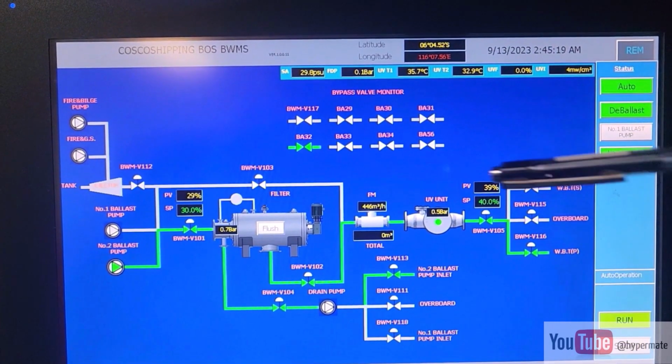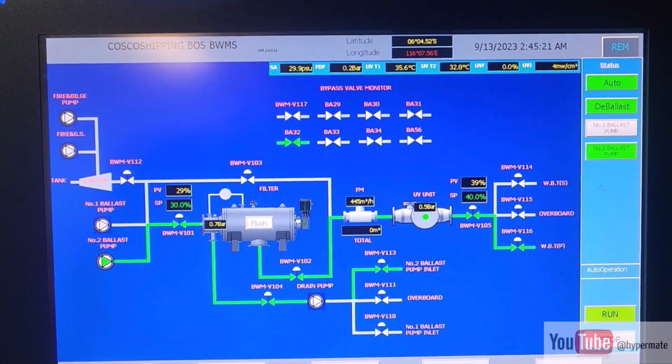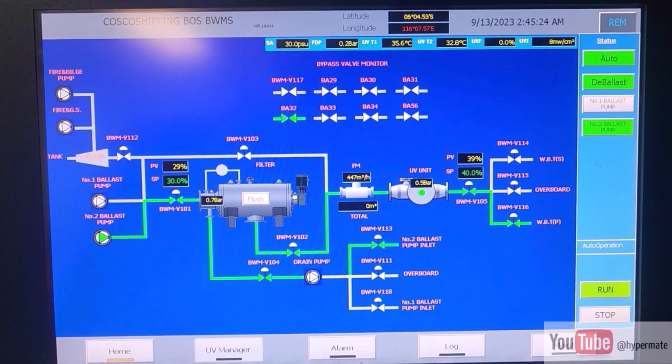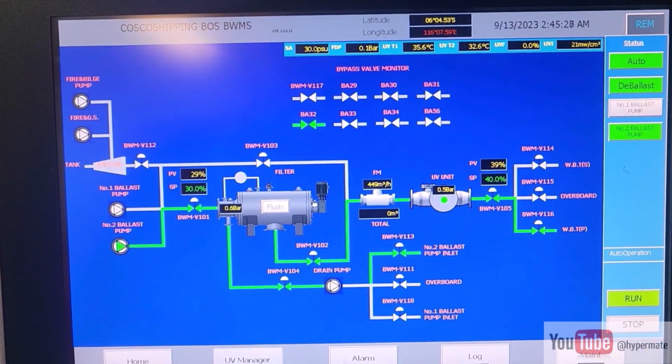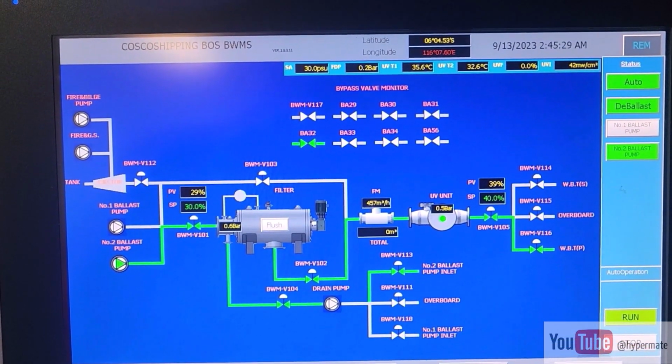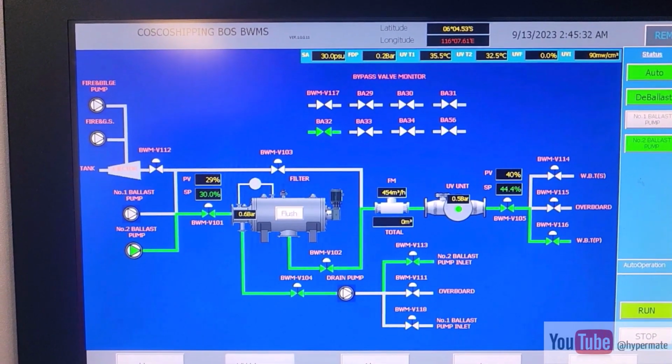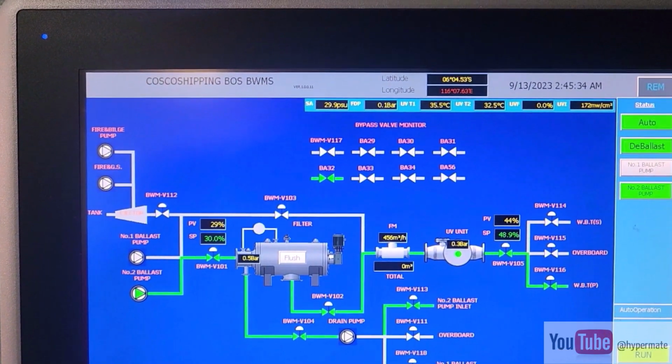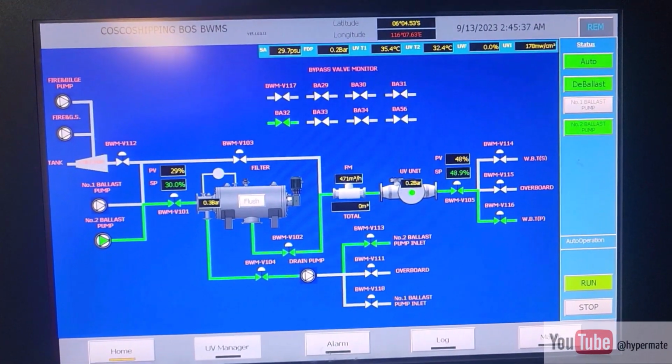Yeah, the pump started working well. Flow is good, 4 cubic meters. I remind you, this is a double bottom tank. When I pump out a normal one, the side tank for example, the pressure is much higher. And the capacity of the ballast pump is 750 cubic meters per hour.